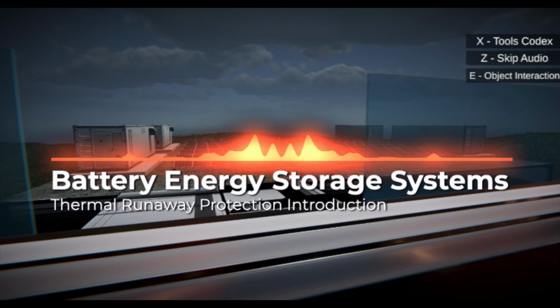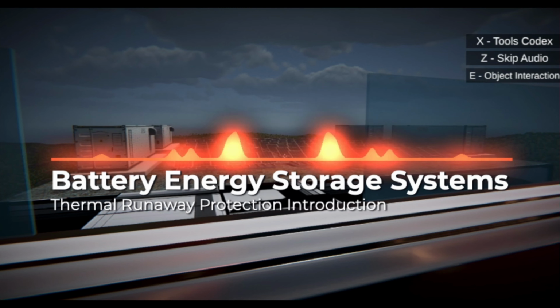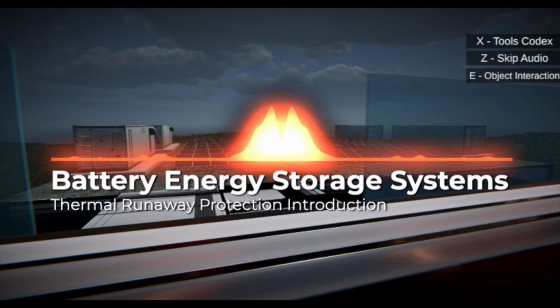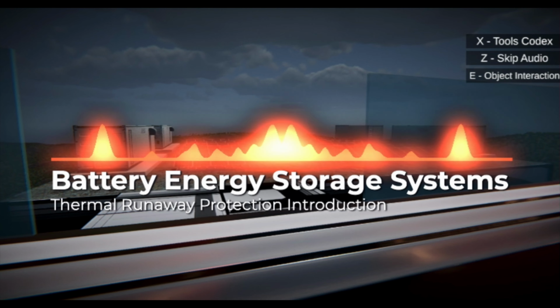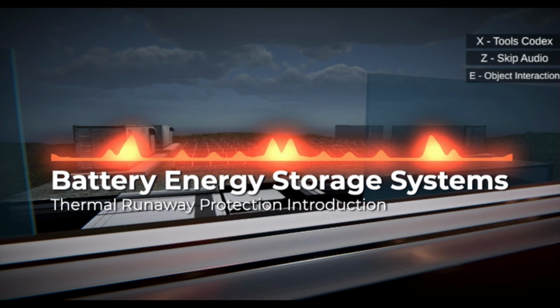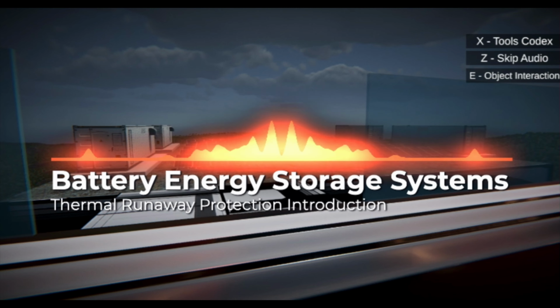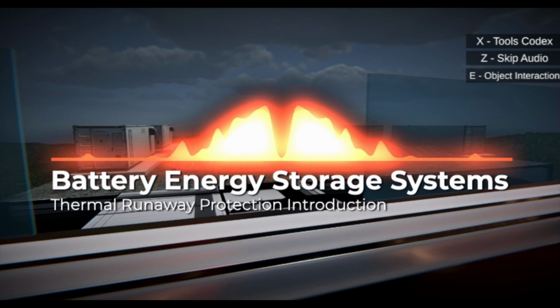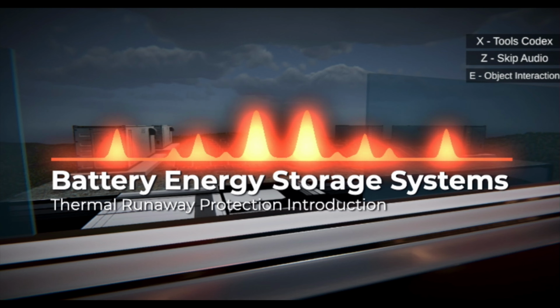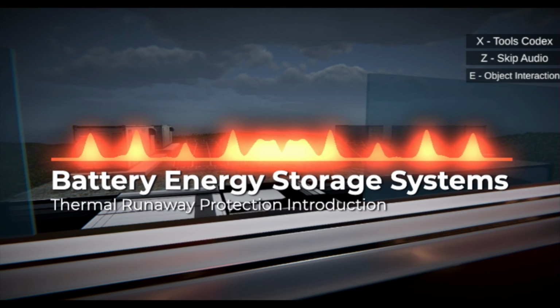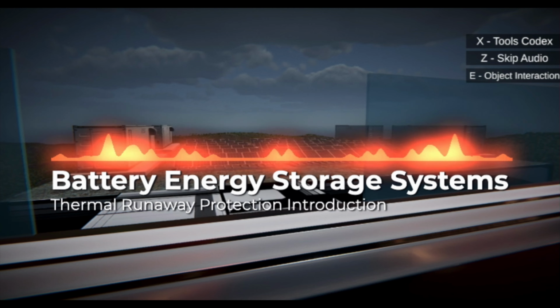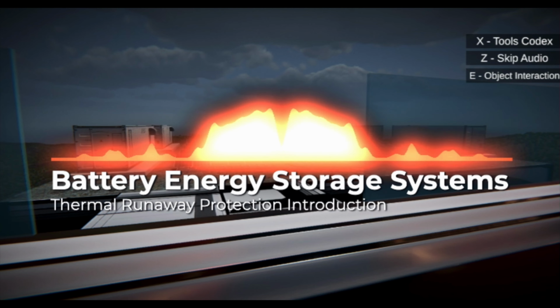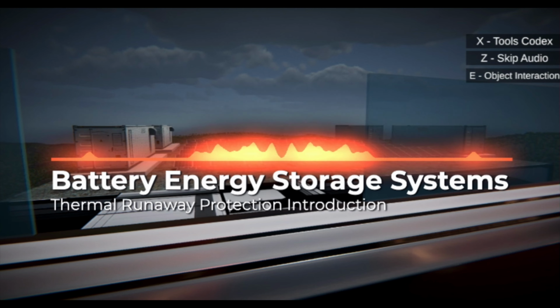Enhancing overall system reliability, let's now shift our focus to the advanced design characteristics and functionality of UVR, under voltage release, and shunt trip mechanisms on breakers and coils, further emphasizing their crucial role in controlling various components within BESS installations. UVR mechanisms monitor the voltage levels in the system and release the hold on the breaker's operating mechanism when the voltage drops below a predetermined threshold.